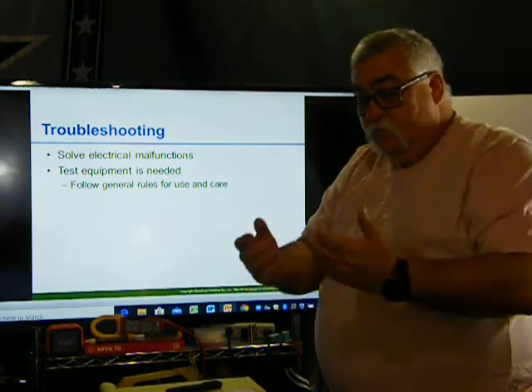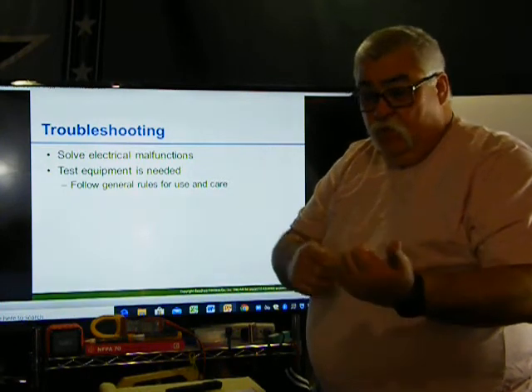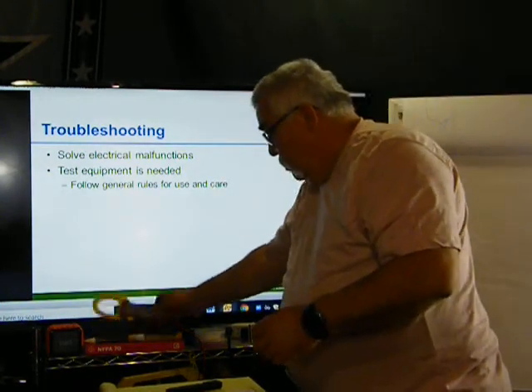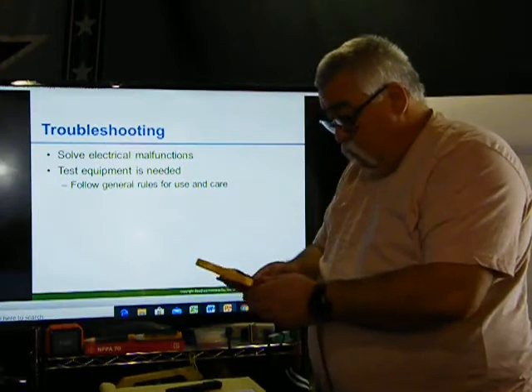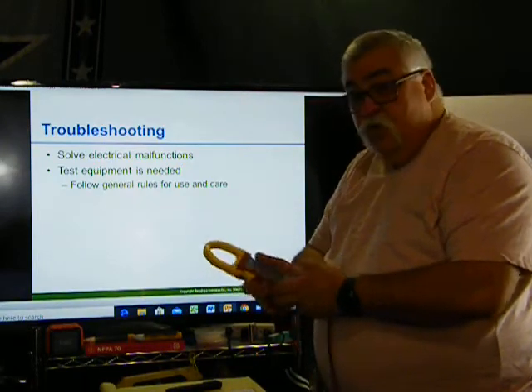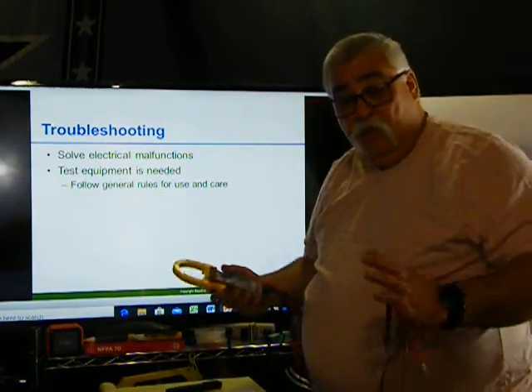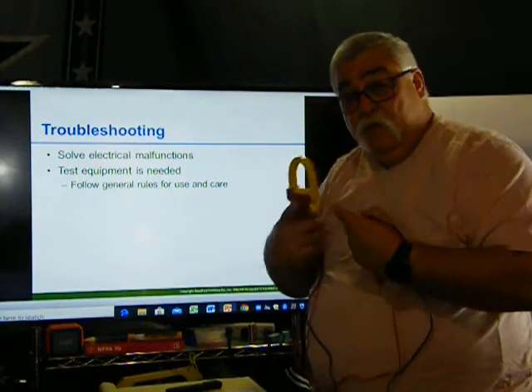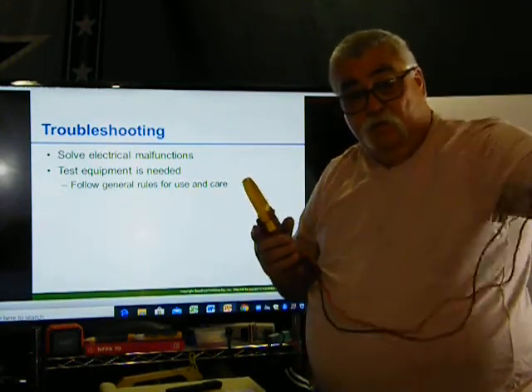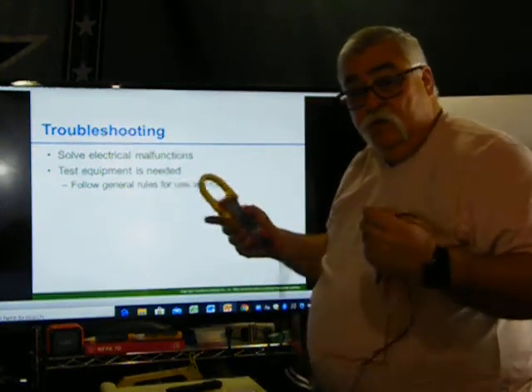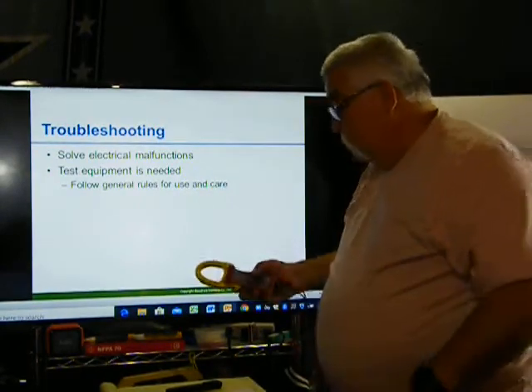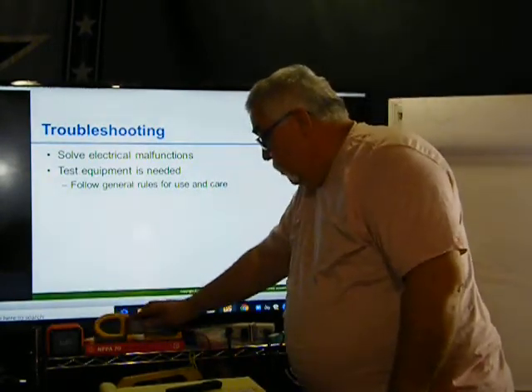Okay, go check. Take the wires out, do resistance, get my meter, put it on ohms, and do an ohm test on the wires. Make sure I don't have a short circuit or a ground fault. Is it going that way, or is it going that way? So now I can tell which way to start looking for where the power may be.